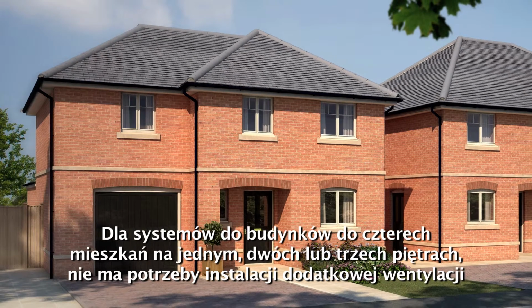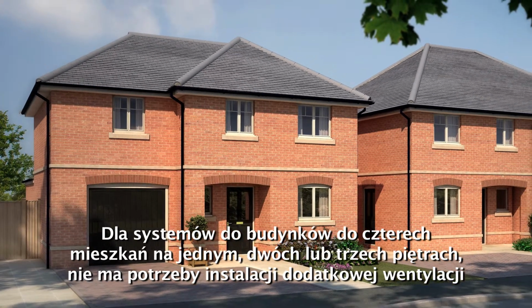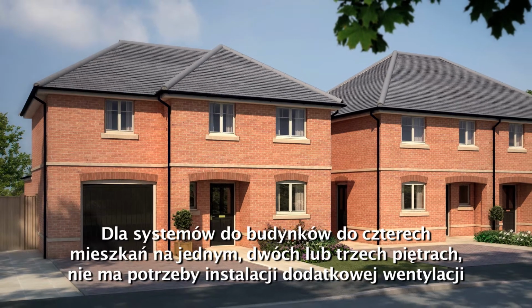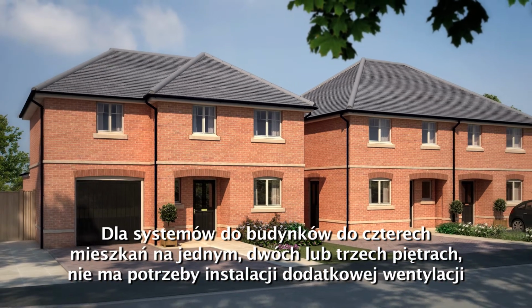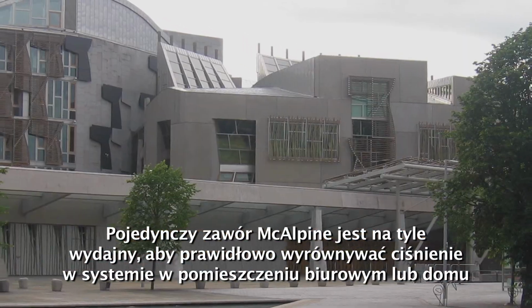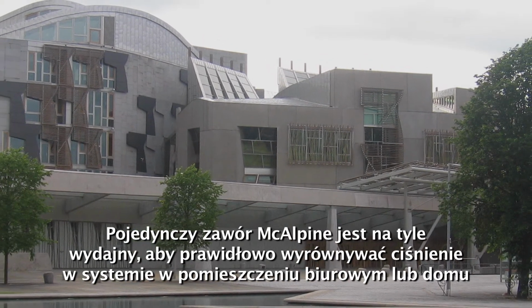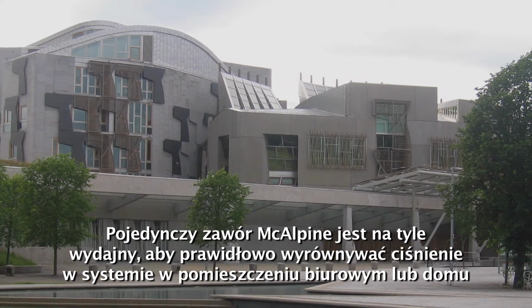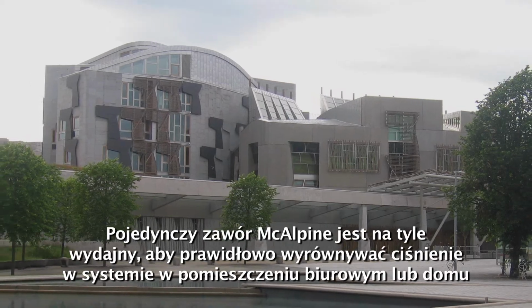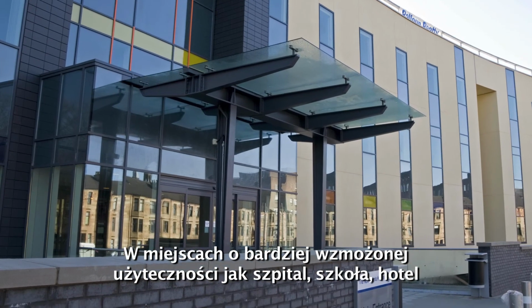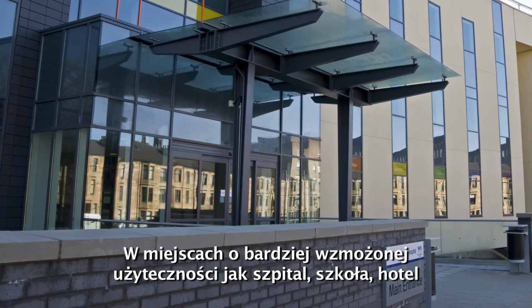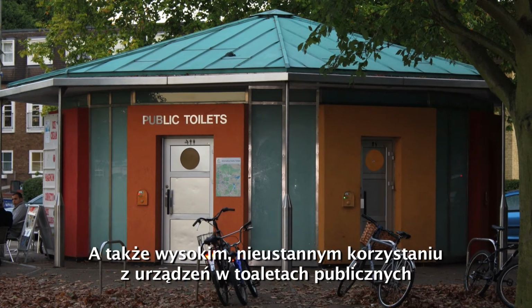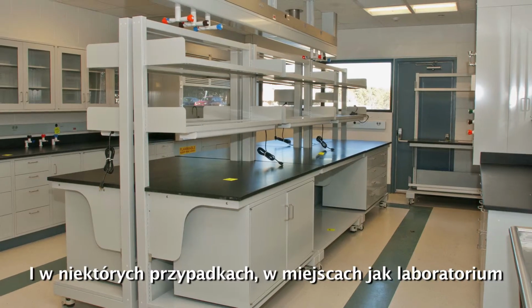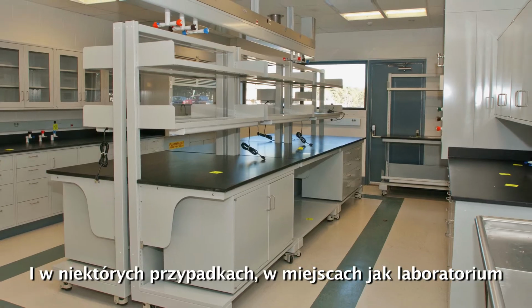For systems up to and including 4 dwellings that are 1, 2 or 3 stories in height, additional drain venting is not required. A single McAlpine AAV has the capacity to maintain pressure in an intermittent running system, such as a house or office, a frequently running system, such as a hospital, school or hotel, a continuously running system, such as a public toilet, and in special circumstances, such as a laboratory.